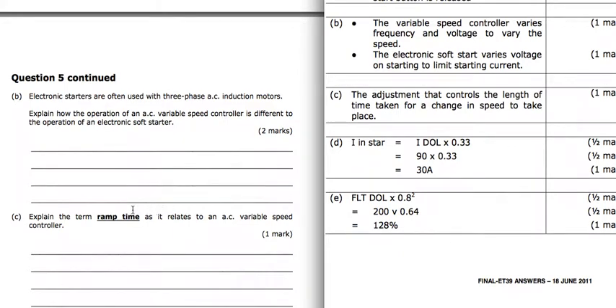Electronic starters are often used with three-phase AC induction motors. How is the operation of an AC variable speed controller different to an electronic soft starter? Well, an electronic soft starter is just all about the starting, as the name implies, and so it varies that voltage to limit the starting current, whereas the variable speed controller varies the frequency and the voltage to vary the speed. So when it's running, we can vary that frequency and voltage together, and we can change the speed of the motor.